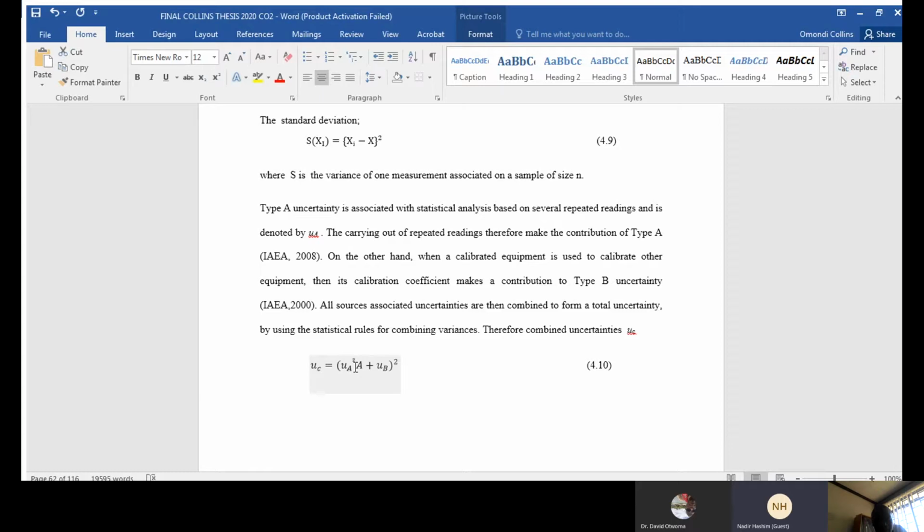Well, if you take repeated measurements, on the same settings of your instrumentation, that gives you statistical uncertainties. However, if you vary your measurements, for example, you set your kV to, let's say, 50, but the instrument does not give you exactly 50 kilovolts. So if you want to determine the systematic uncertainty, you vary the kV, maybe plus or minus a certain percentage, and then you take the measurements. So that gives you some idea of systematic uncertainty in your final readings. I don't know if that makes sense to you.